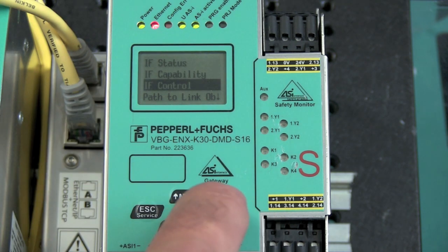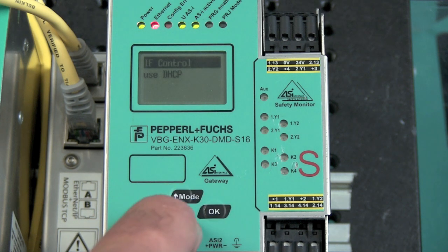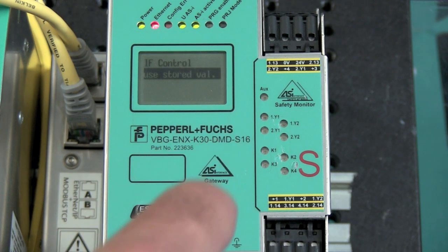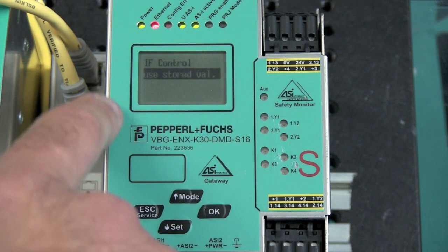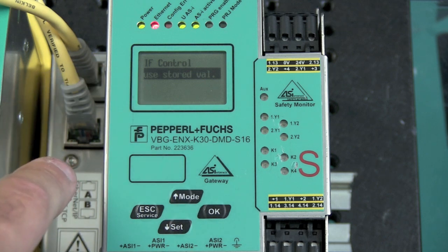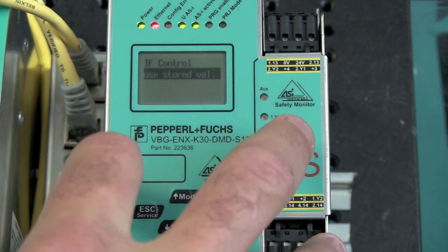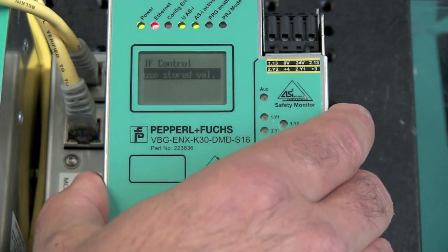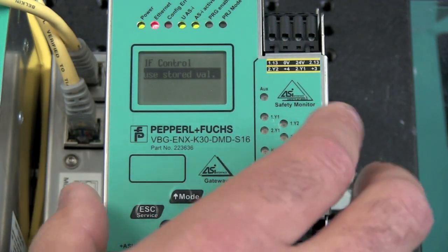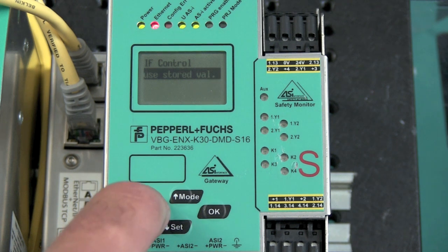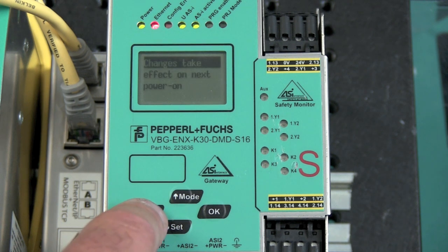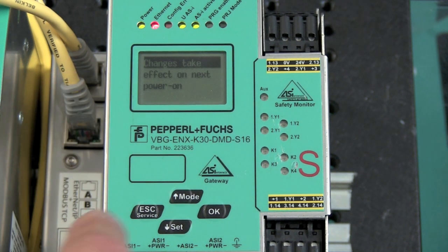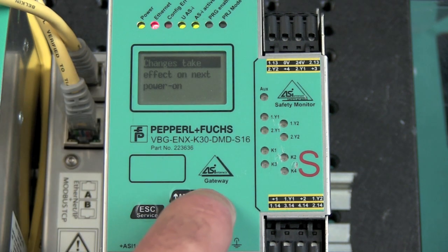So, I go into IF control, arrow down to use DHCP, and then click OK. It will change the setting to use stored value. So, any IP address, subnet mask and gateway that I put in the gateway will now be stored permanently. Hit escape. It will tell me that the settings will only take effect on power-up, which is fine.